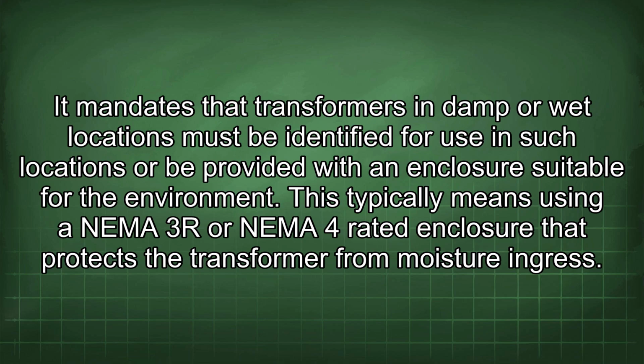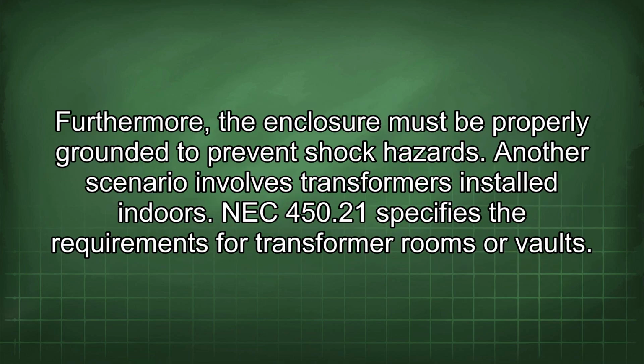This typically means using an NEMA 3R or NEMA 4 rated enclosure that protects the transformer from moisture ingress. Furthermore, the enclosure must be properly grounded to prevent shock hazards. Another scenario involves transformers installed indoors. NEC 450.21 specifies the requirements for transformer rooms or vaults.